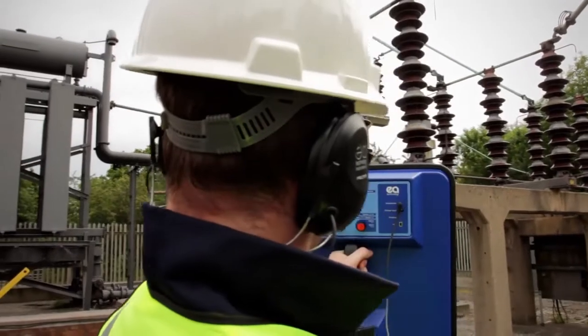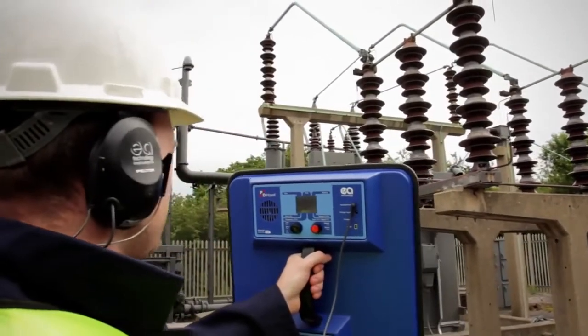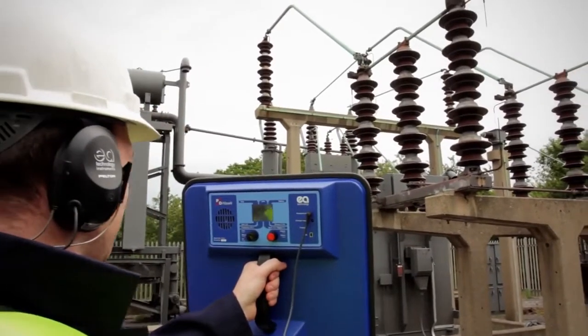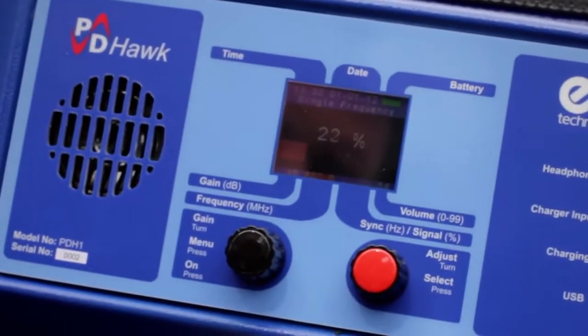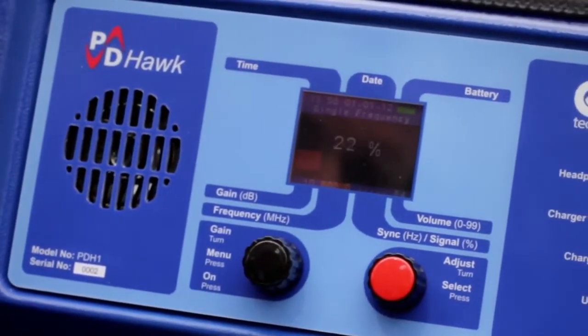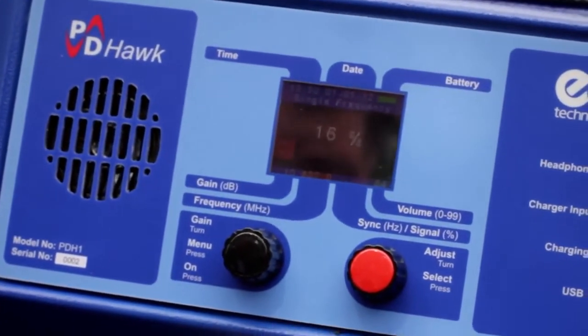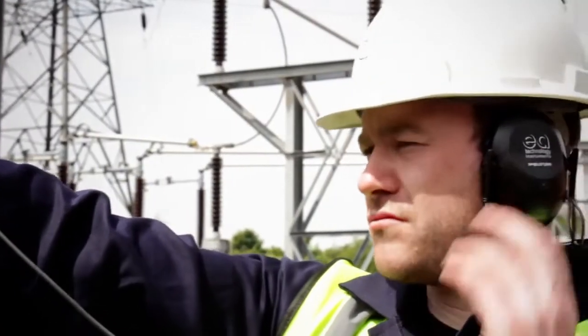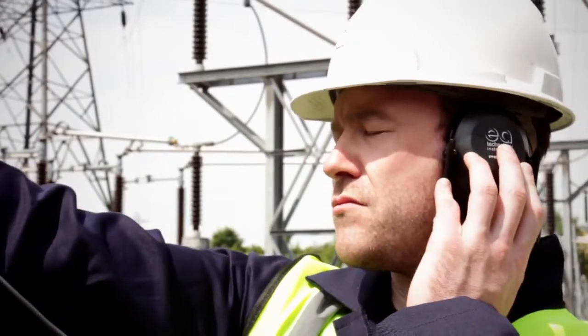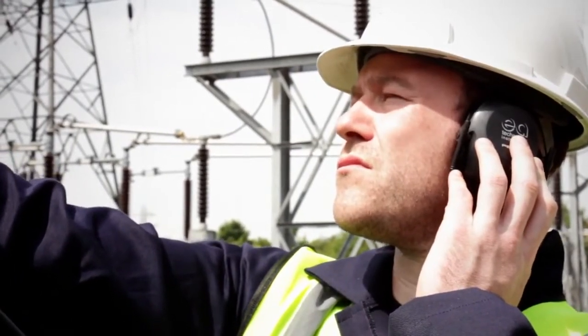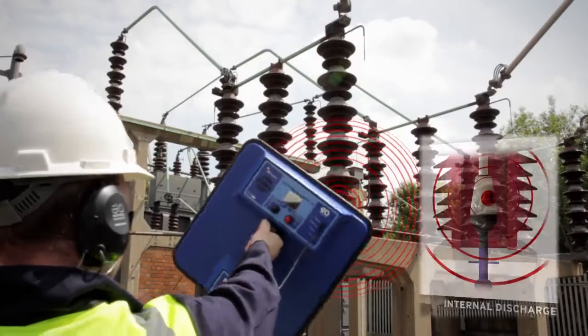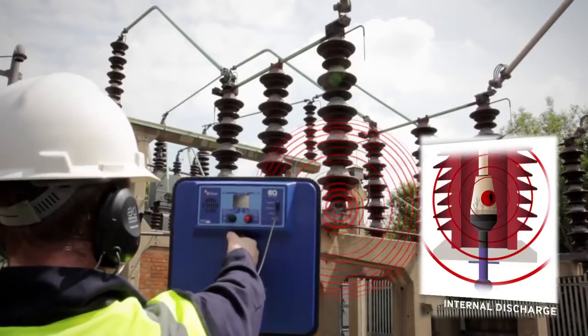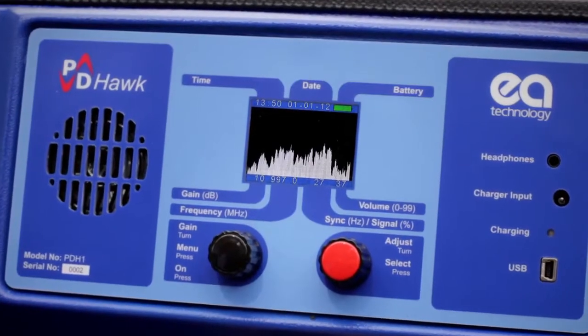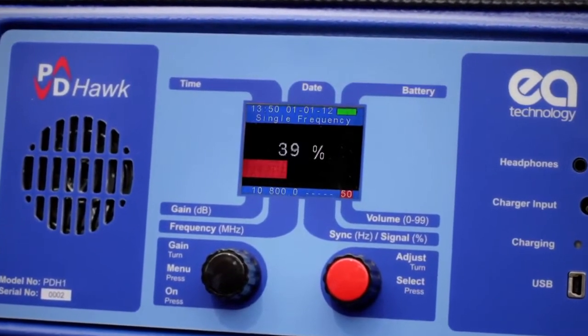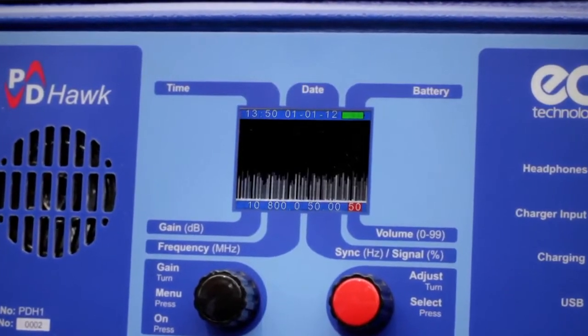The internal PD activity we need to identify is best located in the 800 MHz range. Here we see that the readings in this range peak and decline as the instrument begins to focus in on the source of PD. The engineer can also hear the change in noise over headphones. It is then a simple task to identify the source of the PD activity and view it in terms of frequency, magnitude, and pulse timing.